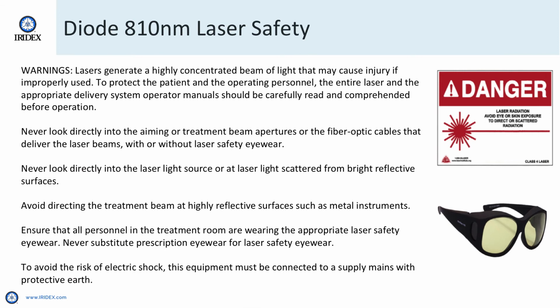When looking at an 810 nanometer diode laser, we must look at laser safety. Lasers generate a highly concentrated beam of light that may cause injury if improperly used. To protect the patient and the operating personnel, the entire laser and the appropriate delivery system operating manuals should be carefully read and comprehended before operation. Never look directly into the aiming or treatment beam apertures or the fiber optic cables that deliver the laser beams, with or without laser safety eyewear.